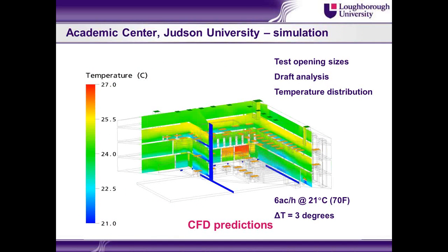Back to computer simulation then, and the use of computational fluid dynamics. So looking at a section of this building here, what we were doing here was to test the opening sizes, make sure that they were large enough when operating in the natural ventilation mode. We're looking at the draft analysis and the comforts of the airspeeds around the occupant's ankles, and look at temperature distribution. Again, we sized these openings according to the stack driving pressure that was acting at any height. We've got some problems here whereby the openings aren't large enough. I think there were a lot of computers in this space here, so we need to treat that separately.